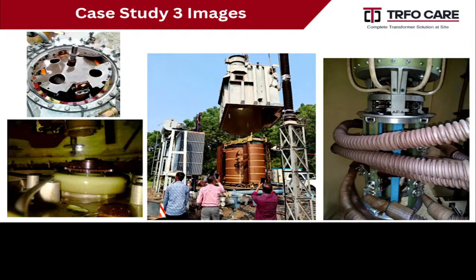The only problem was the OLTC diverter. There was a huge amount of oil, and water content was observed in the OLTC diverter chamber. So nothing had happened to the core coil assembly. We called the OLTC manufacturer, got an exact same OLTC made, and replaced that OLTC at site, near the Bhusawal region. This transformer has also been running successfully for the last 8 months.